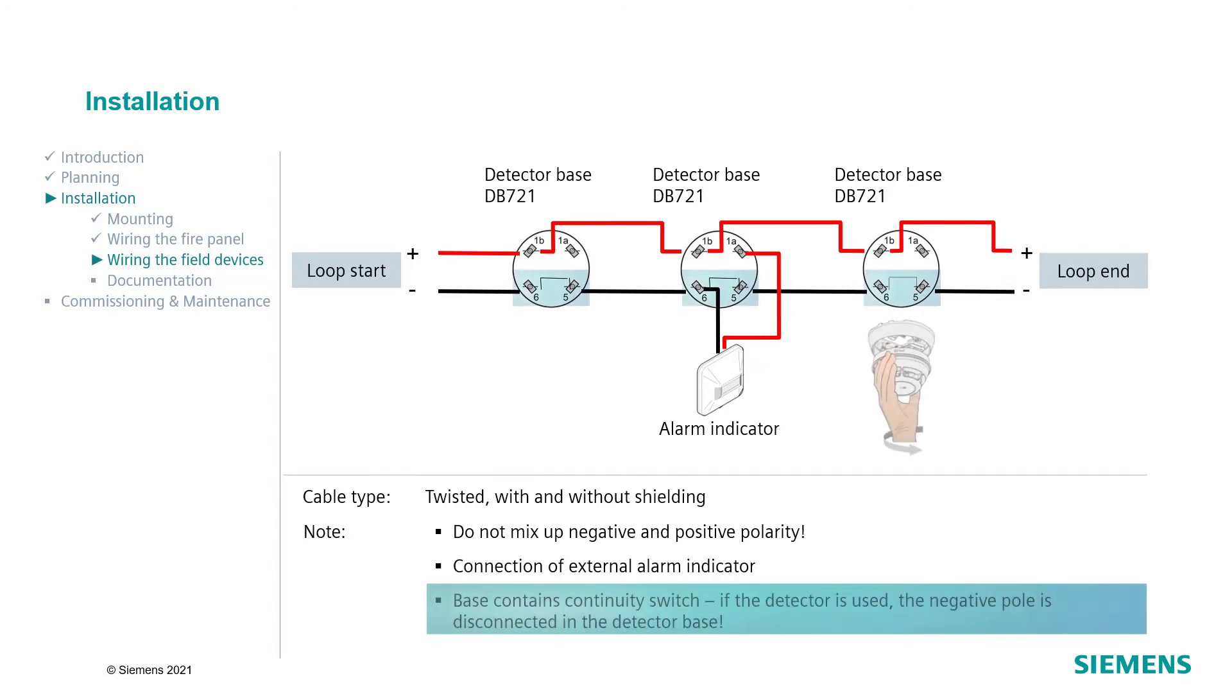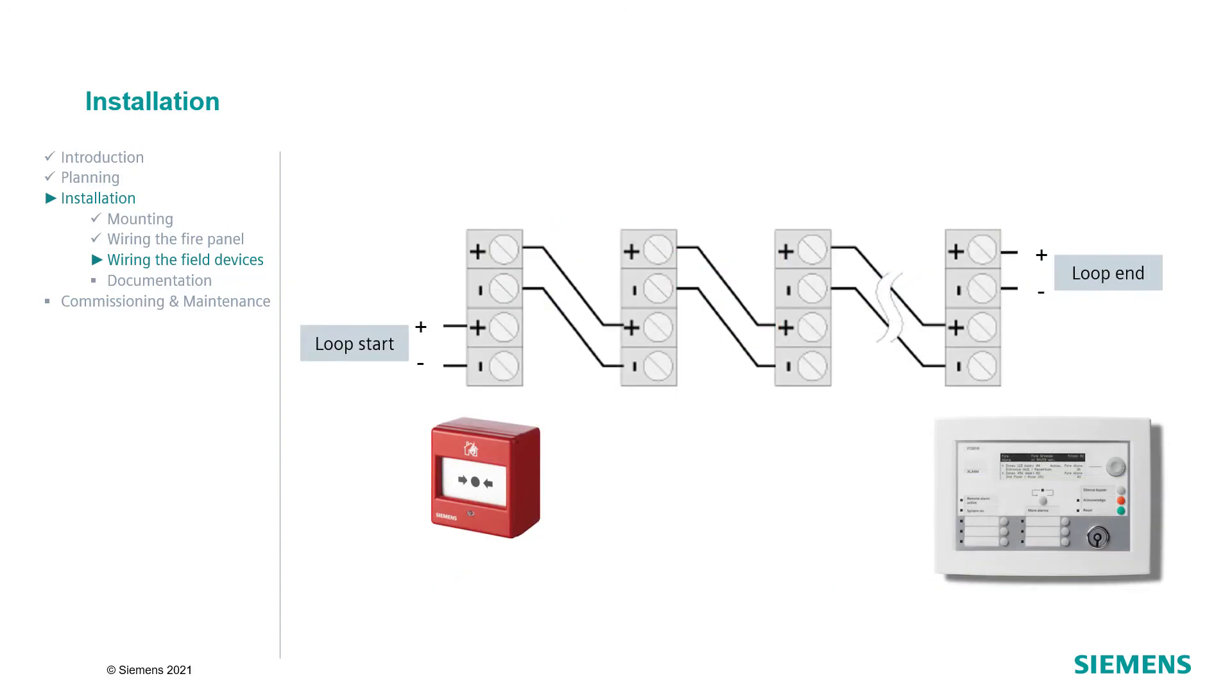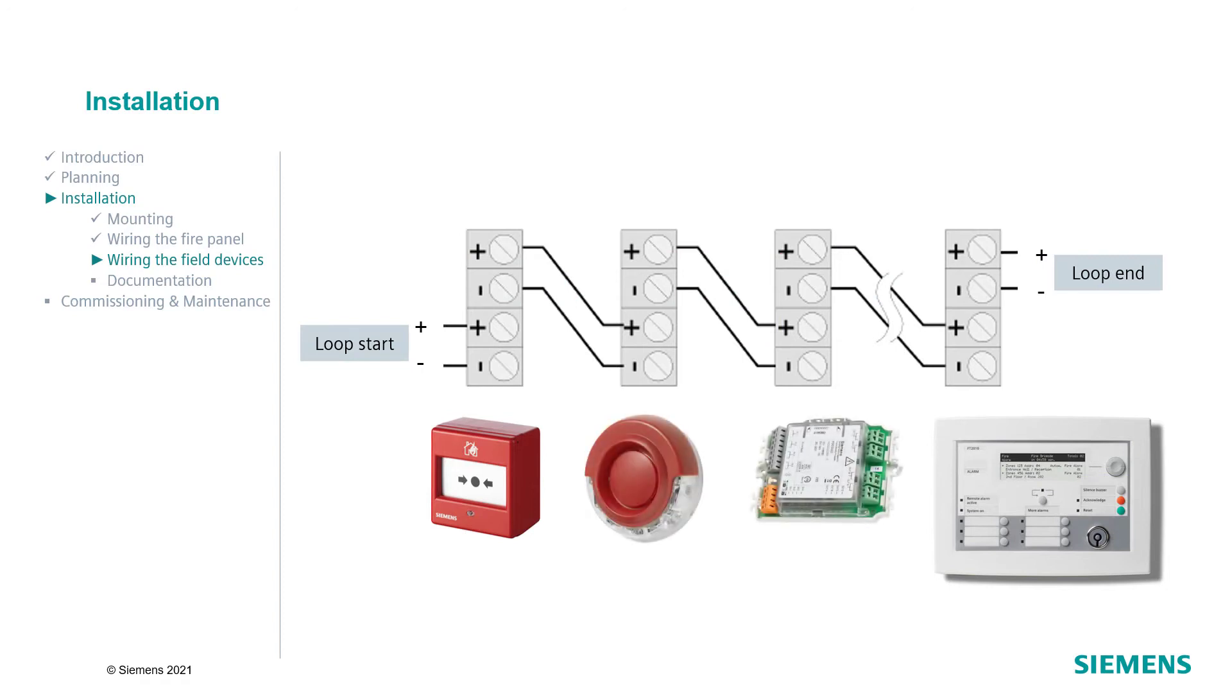Each base is equipped with a loop contact, that means a continuity switch. This continuity switch ensures that the loop remains unbroken when the detector is removed. All other field devices have a screw or clamp terminal for the loop connection. Make sure not to mix up negative and positive polarity.